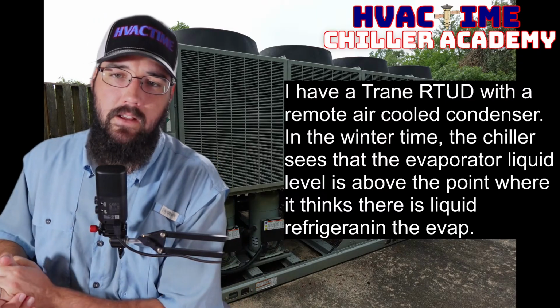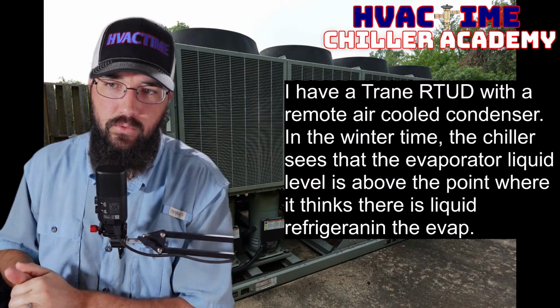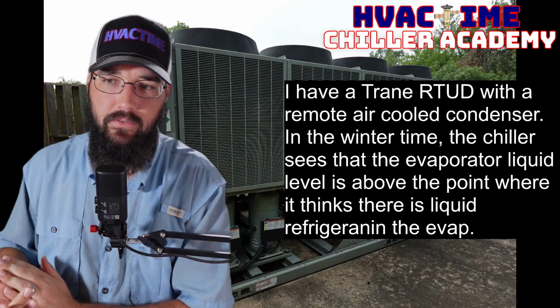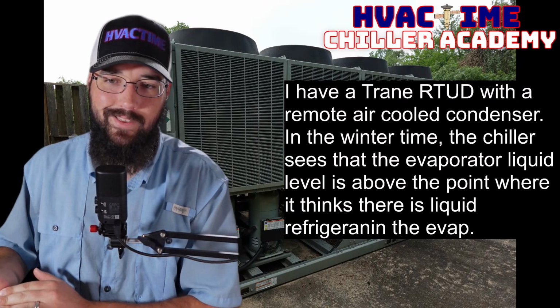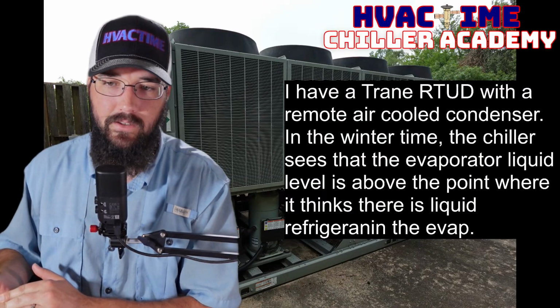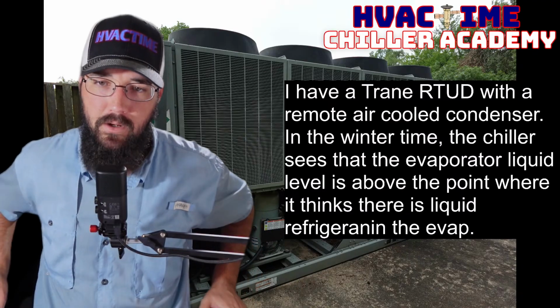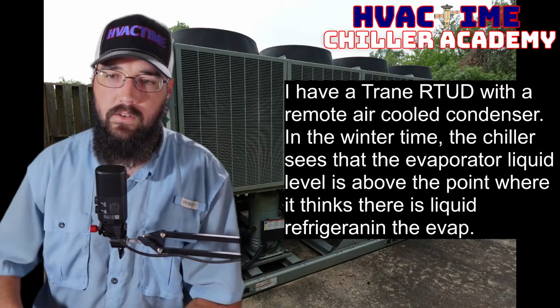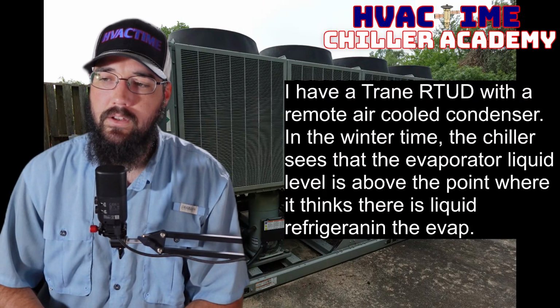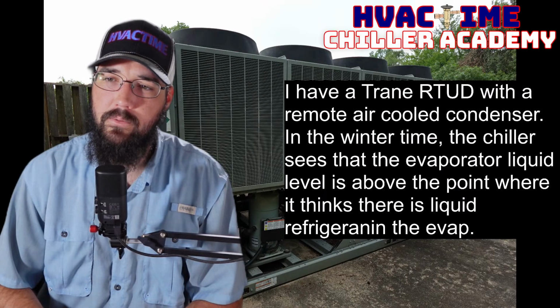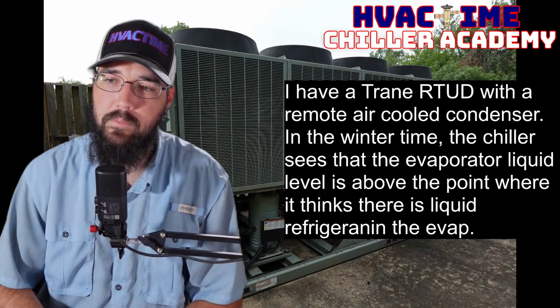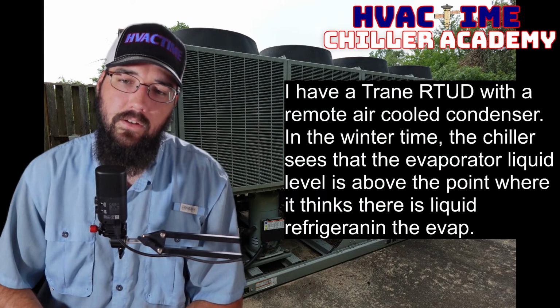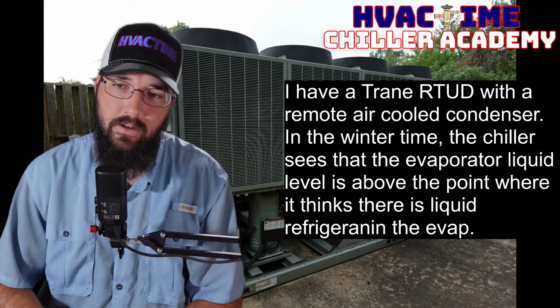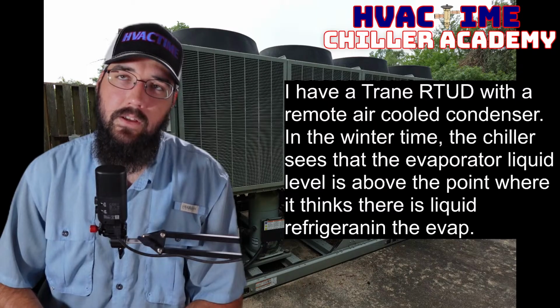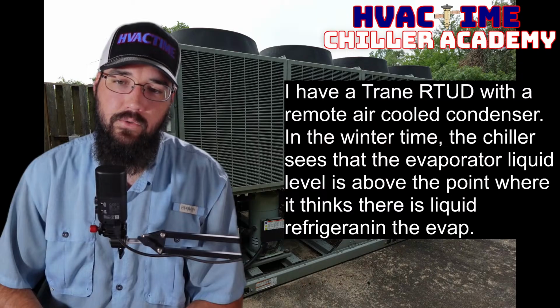Okay. I have a Trane RTUD with a remote air-cooled condenser. In the wintertime, the chiller sees that the evaporator liquid level is above the point where it thinks there is liquid refrigerant in the evap. So it is above the point where it thinks there is. One thing I do want to clarify: the chiller sees that the evaporator liquid level is above the point where it thinks there is. So it is seeing, as in at the time of pump down it's seeing this, or it is seeing a high liquid refrigerant level and is trying to control based off of that high level?